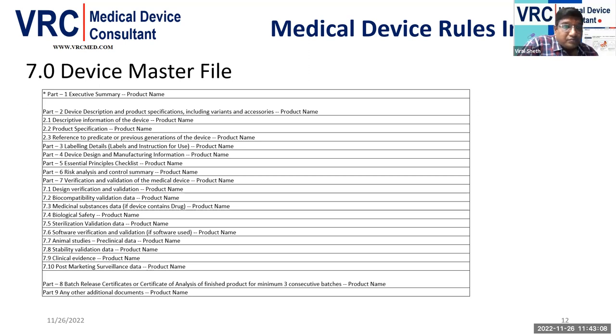Part 7 has 10 sections covering design verification and validations. Biocompatibility is a minimum requirement for every device, depending on the duration of contact with the patient. So first, when claiming biocompatibility validation data, we should identify what types of biocompatibility tests are applicable to our device.